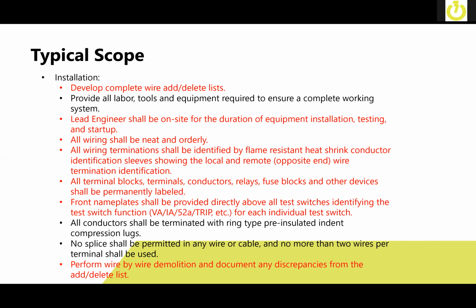From an installation standpoint, as I mentioned earlier, we like to develop complete wire add and delete lists. What that enables our engineers out in the field to do is put the drawings to the side and go wire by wire. We start at one end, we determinate it or cut it depending on the application that's required. We follow it to the end device, and then we make sure that it matches our delete list completely. If it doesn't, we stop and flag it for the lead engineer to take a look at, and the crew can keep on working on the demolition while the lead engineer figures out what changes may need to be made to the design. We also provide all tools, labor, and equipment required to ensure the complete working installation.